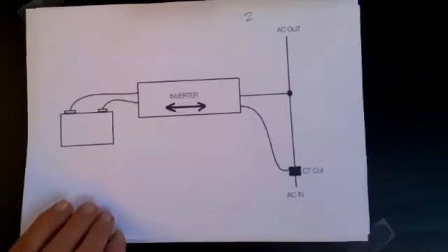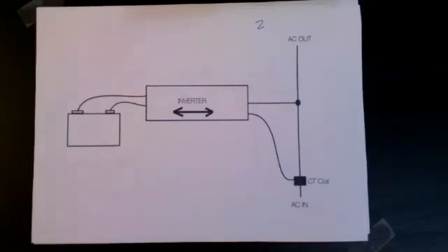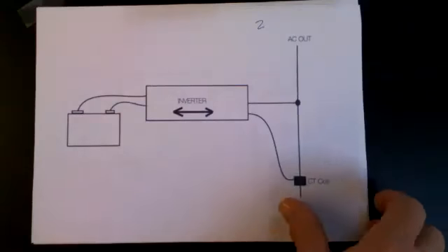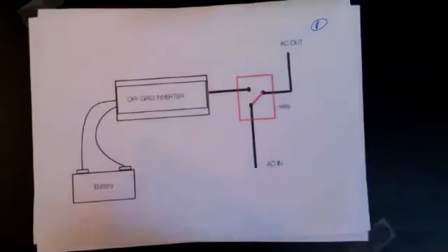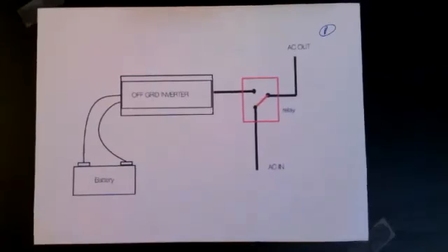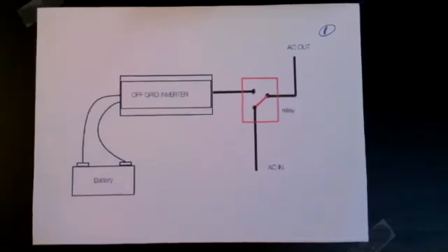So looking at our inverter and looking at some of the more modern inverters, and I mentioned that because the first drawing I showed you, the first one, I'll just go one back, many inverters still sold in South Africa, and a lot of the cheaper ones, work in this way. You have an inverter, you have a relay. When it's running off grid, clonk, the relay goes through the inverter. There are lots of problems by doing it this way. And the problem is you're governed by the size of the inverter. If your house needs 5 kilowatt, 10 kilowatt, you have to have a 10 kilowatt inverter. Whereas the way we do it, it doesn't quite matter.